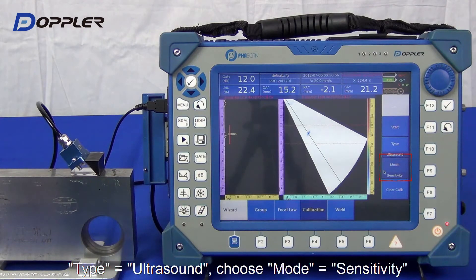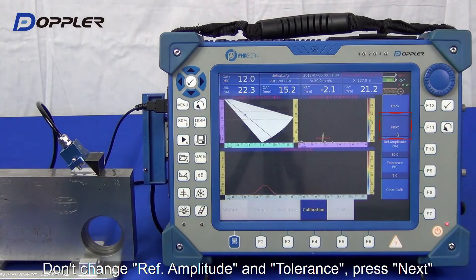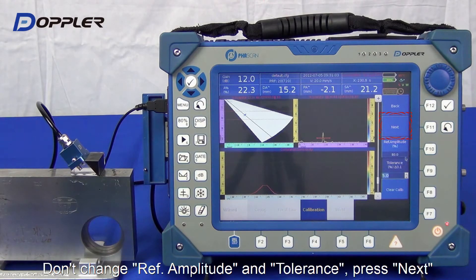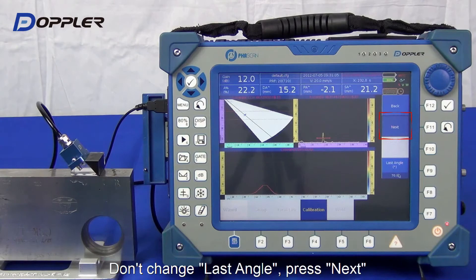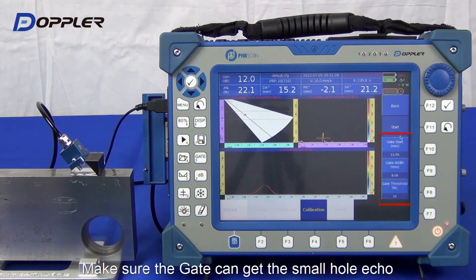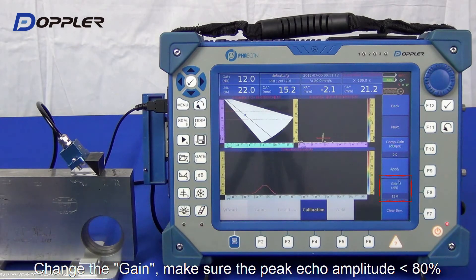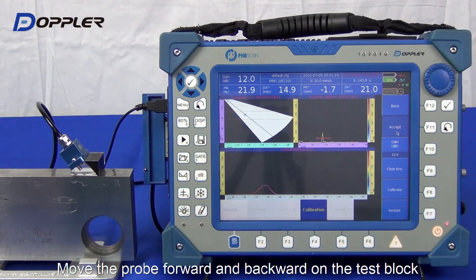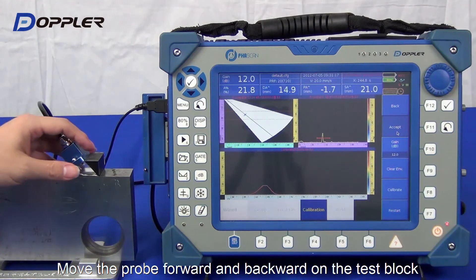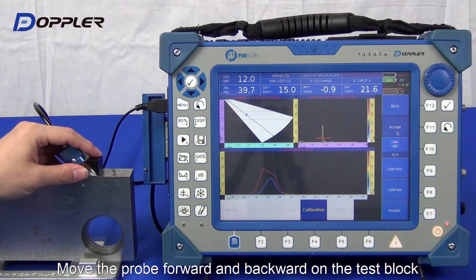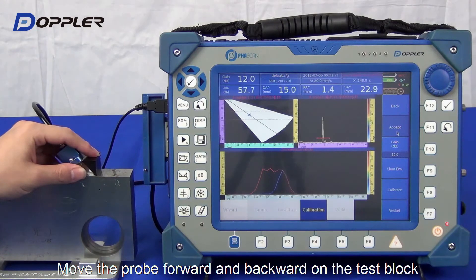Select Calibration, Ultrasound, Sensitivity, then Start. For most calibration, the Phascan default settings are optimized automatically according to the parameters input. Next, adjust the gate to acquire the peak echo. Gain is adjustable here for an embedded visual. Scan back and forth to smooth out the peak's line.